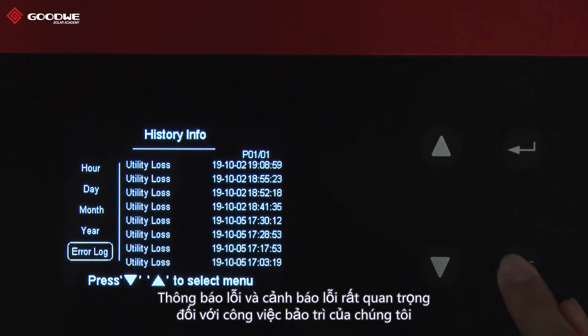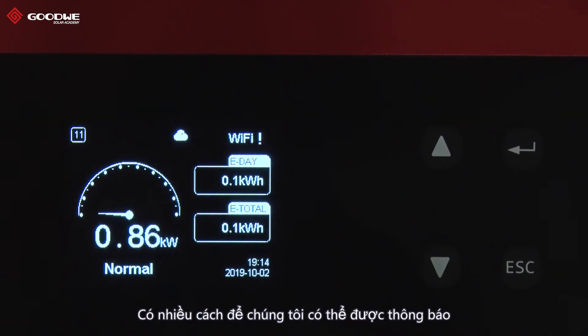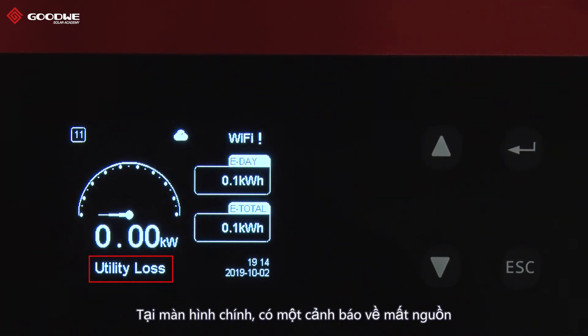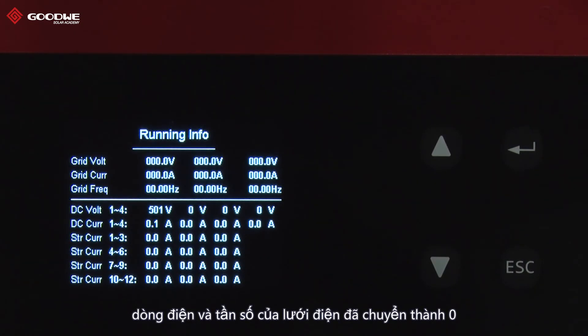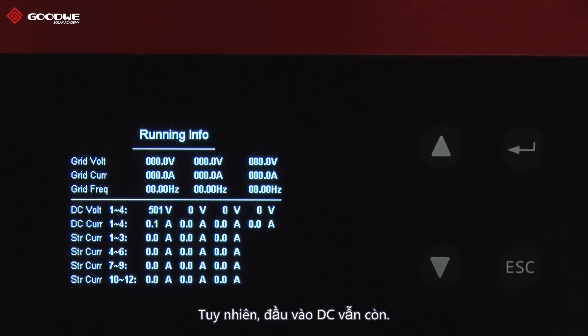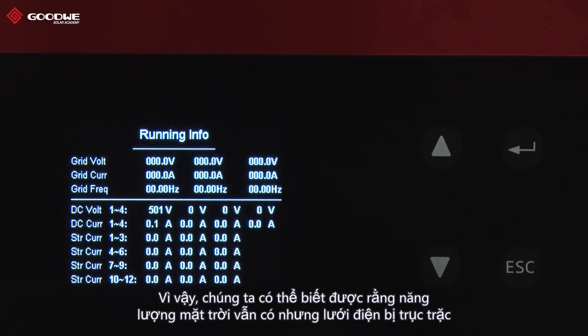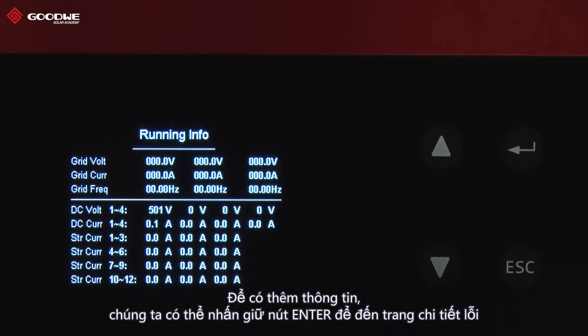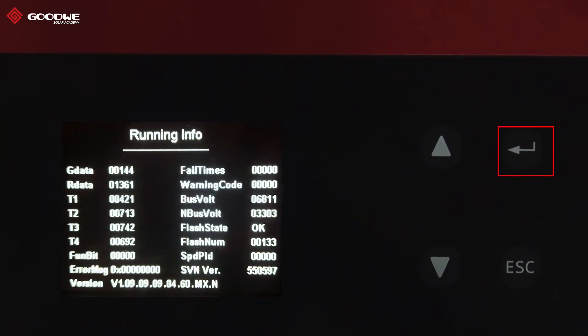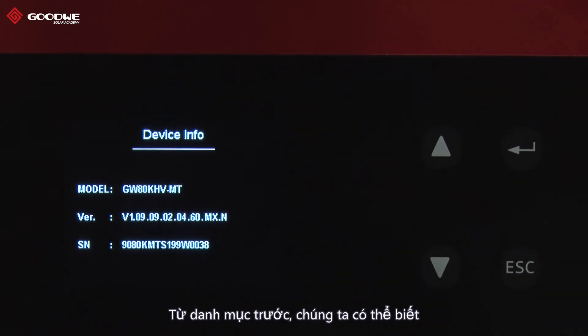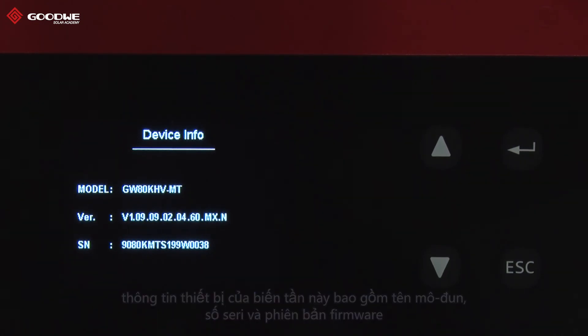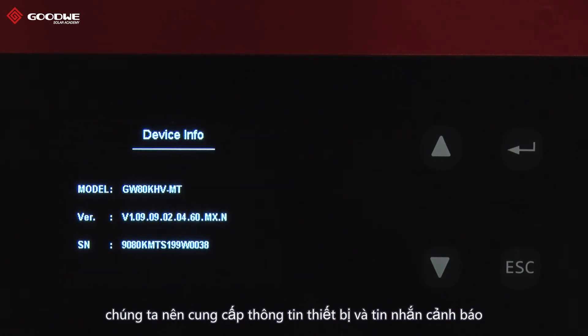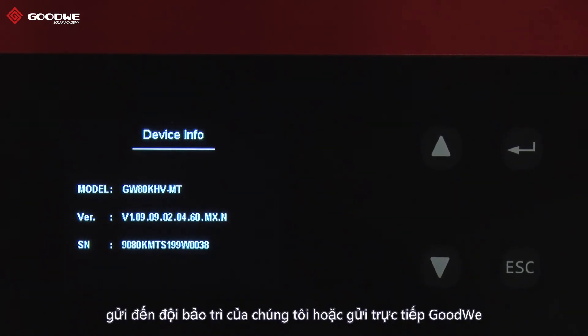Error messages and fault warnings are important to our maintenance work, and there are many ways to get informed. On the home page, there is a warning about utility faults. In running info, we can see that the voltage, current, and frequency of the grid have turned to zero. However, there is still DC input, so we are able to note that there is PV energy while the grid has failed. To get more details, we can press Enter to the fault detail page. From the last menu, we can find this inverter's device info including model name, serial number, and firmware version. To get swift recovery, we should provide the device info and warning message to our maintenance team or GoodWe.